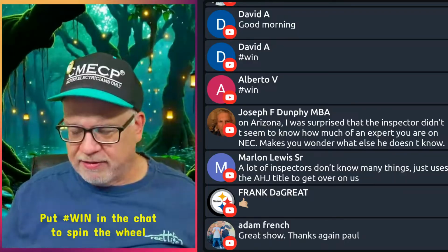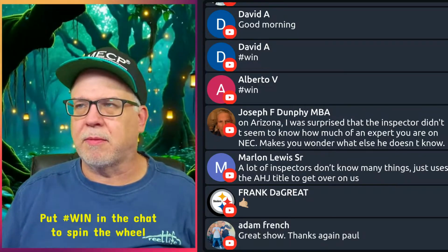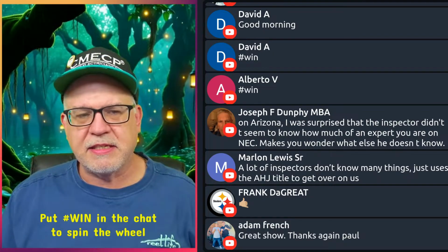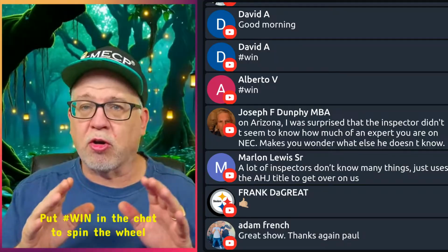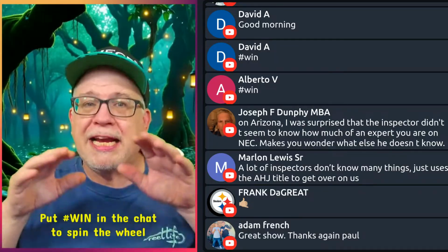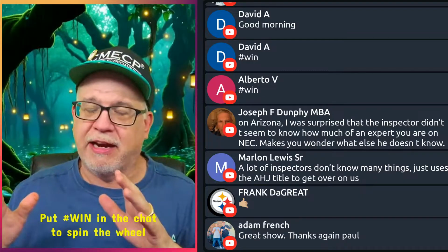Once it starts propagating all over social media, people's heads spin off. You see a nameplate rating that says minimum circuit ampacity, maximum overcurrent device, overcurrent protection, and people freak out, even though this is all based on Article 440. The rules are right in there that the manufacturers use to make these nameplates. It says it right there in 440.